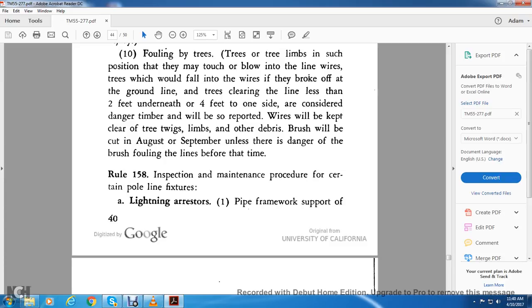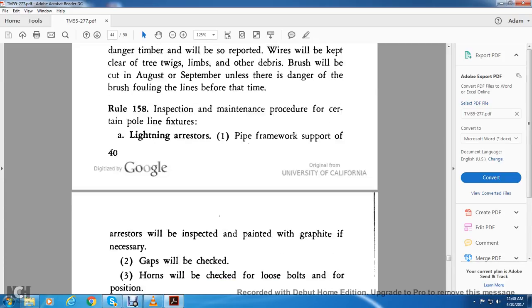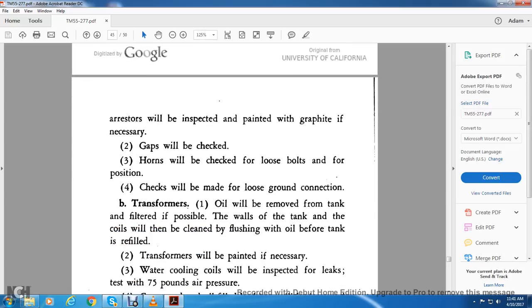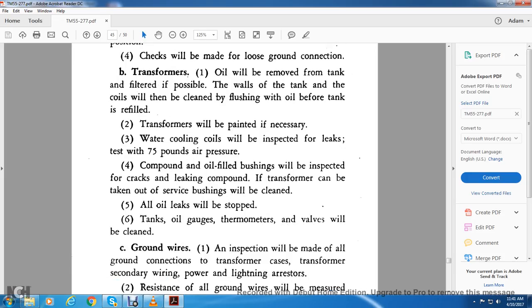Rule 158, inspection and maintenance procedure for certain pole line fixtures. A. Lightning arresters: one, pipe, framework, and supports. The arrester will be inspected and painted with graphite as necessary. 2. Gaps will be checked, and horns will be checked for loose bolts and position. Checks will be made for loose ground connections. B. Transformers: 1. Oil will be removed from the tank and filtered. If possible, the walls of the tank and the coils will be cleaned by flushing with oil before the tank is refilled. Transformers will be painted.